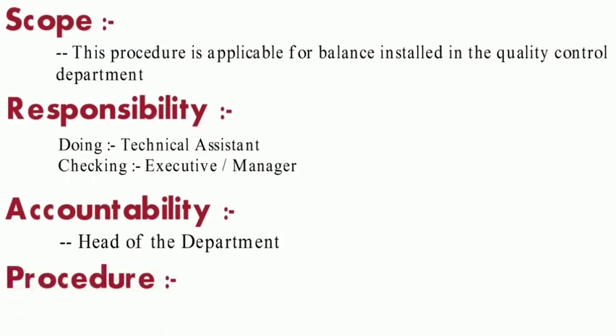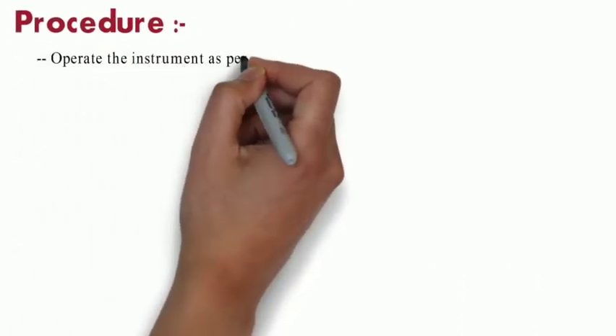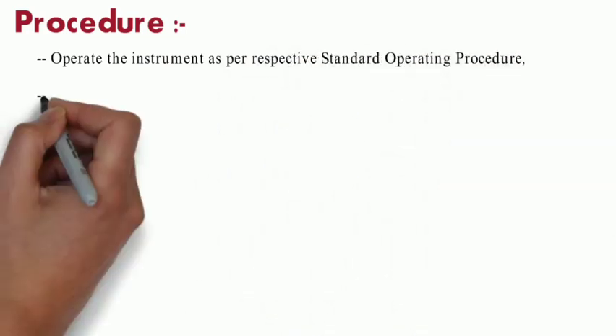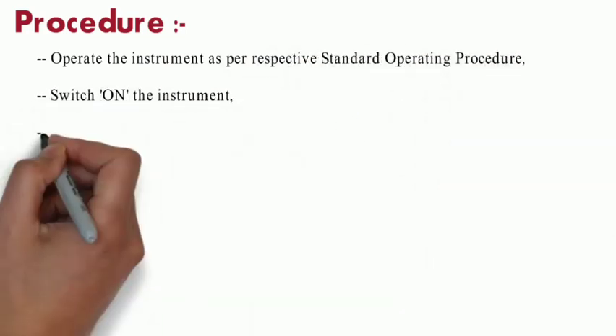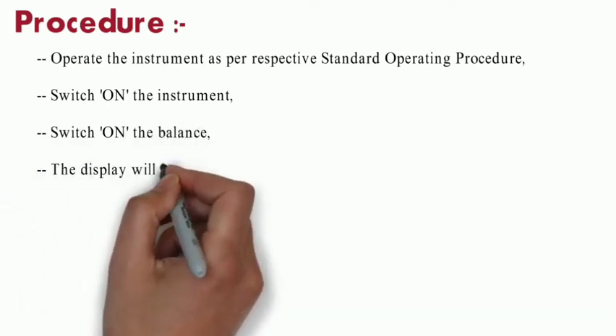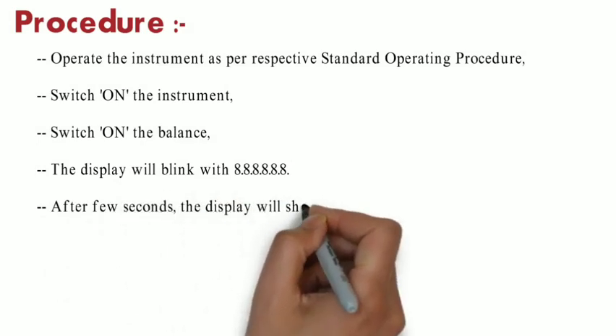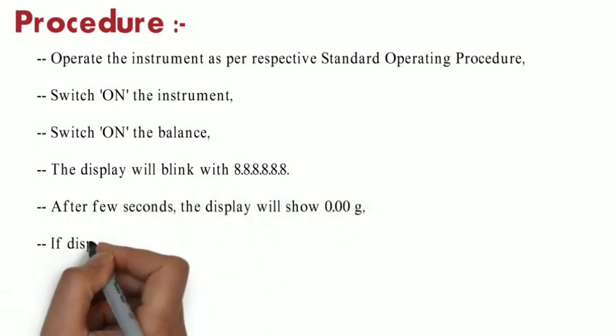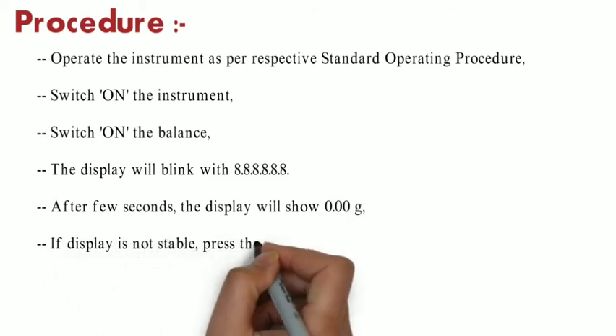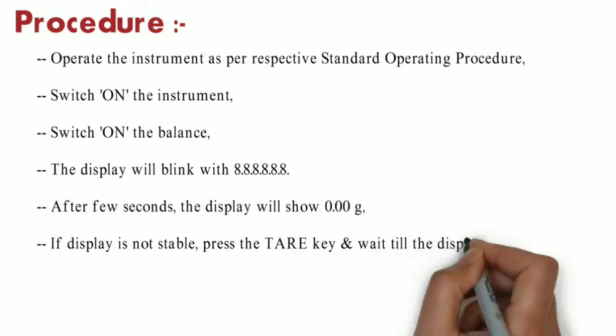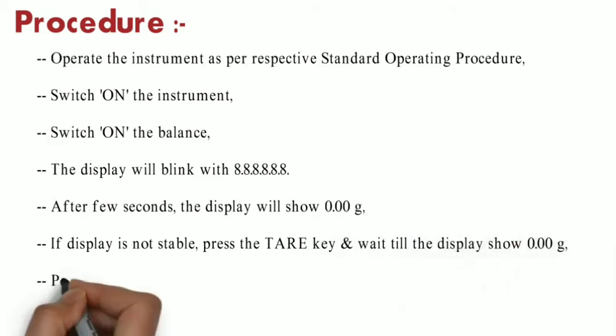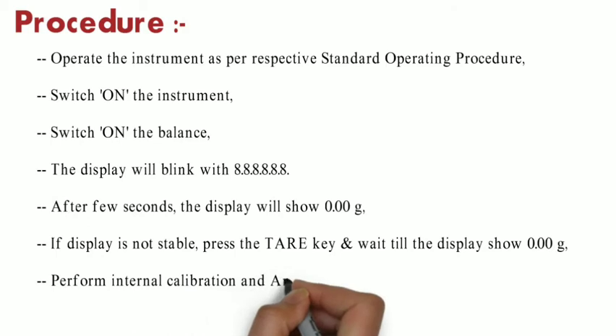In procedure, first we have to operate the instrument as per respective standard operating procedure. Switch on the balance. Display will blink with 8.8.8.8.8.8. After a few seconds, the display will show 0.00 grams. If display is not stable, press the tare key and wait till the display shows 0.00 grams. Perform internal calibration in Annexure 2.